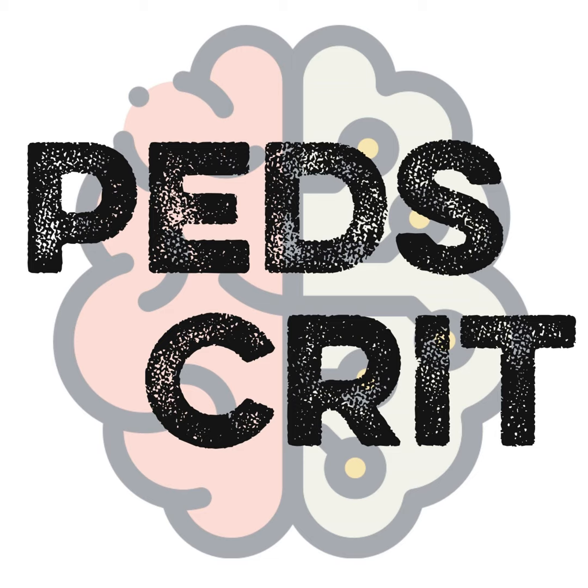As we think about what double triggering is, this is a situation where the patient is usually air hungry and they are taking deep, long breaths to try to get really big breaths. So their inspiratory phase is longer than whatever is set in the ventilator. The patient's taking that nice long breath. The ventilator gives a breath, and in the ventilator's mind, if you will, in the computer, reaches the end of the set inspiratory time and opens the expiratory valve and starts to potentially dump the breath. And so the ventilator has moved on and said, oh, we're now at the next breath. But that flow trigger is still sensing the patient is still inhaling, and so right away it gives another breath. It's a mismatch between the patient's neurally set inspiratory time and the ventilator's mechanically set inspiratory time.